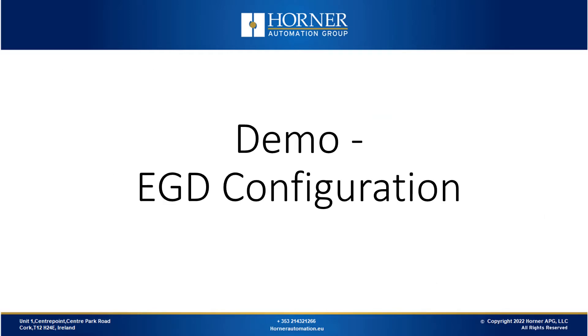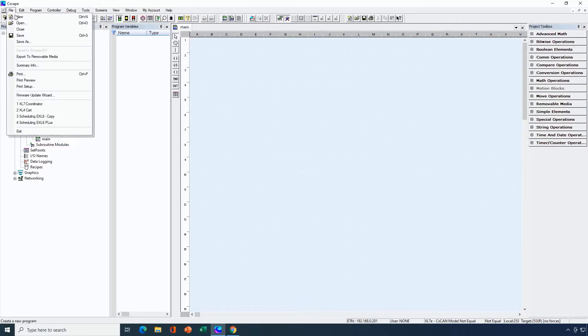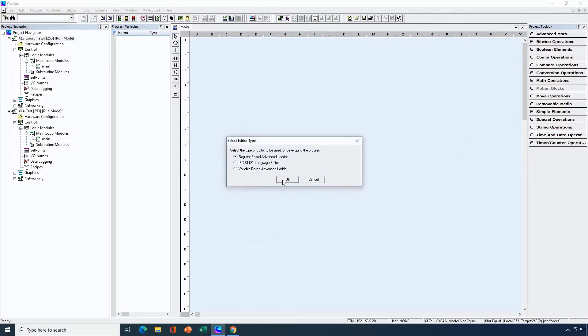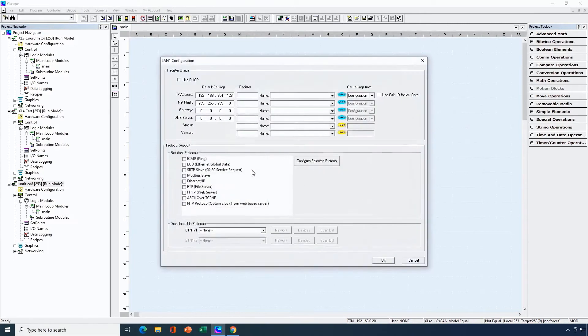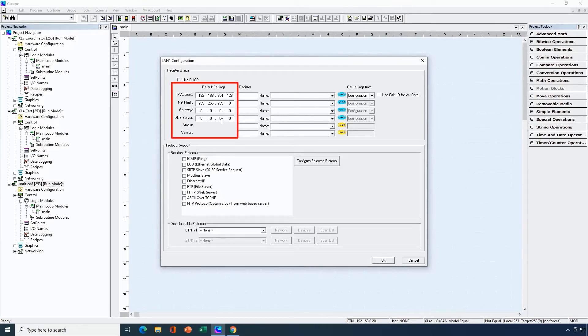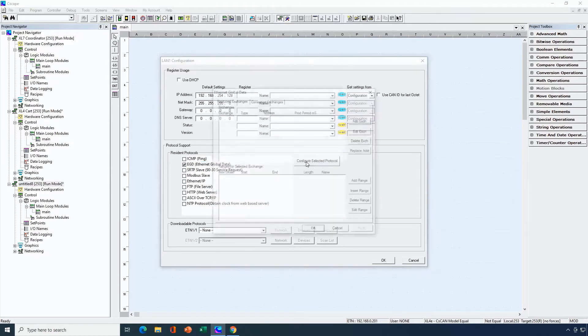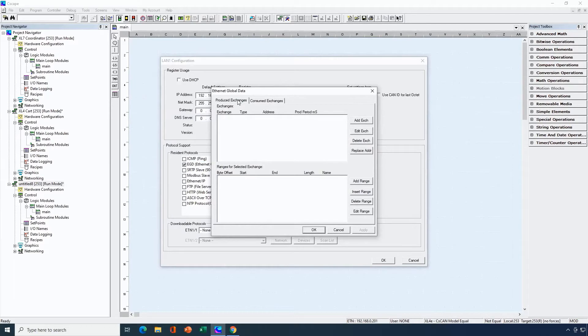Now let's begin our demo where we'll look at that configuration in Cscape. I'll go into Cscape — the first thing I did was create a new file and I'm using register based logic. I'll start by going into hardware configuration and then lan1 config. It works on both lan1 and lan2 if you have an XL7 or an eXL10 or an XLplus for instance. If you're going to use Ethernet global data you need to make sure that Ethernet is set up the way you want in terms of IP address, netmask, etc. Then to set up EGD you just select it on the list of resident protocols and hit configure selected protocol.